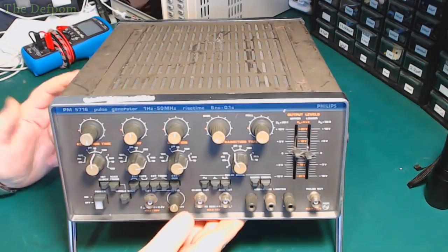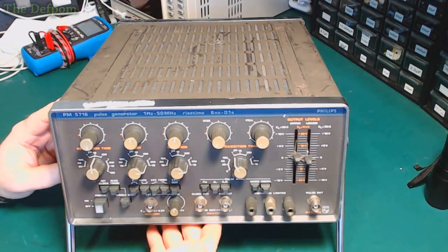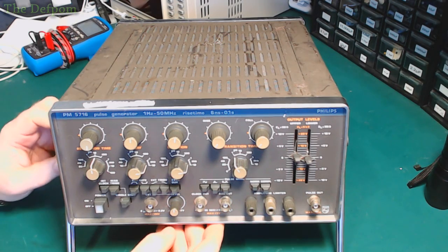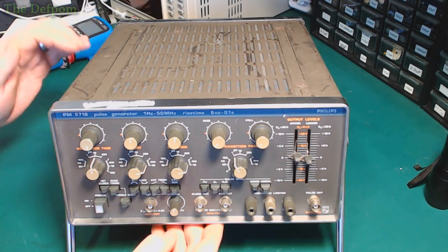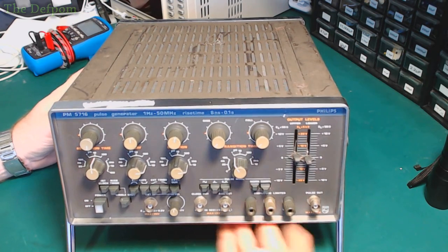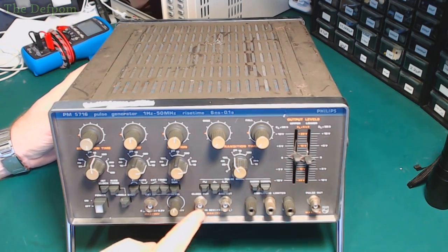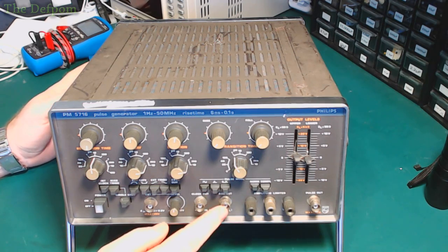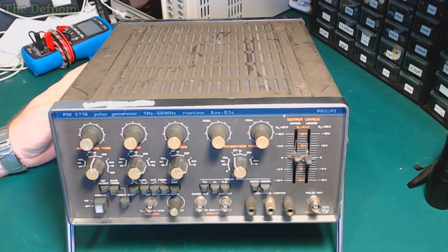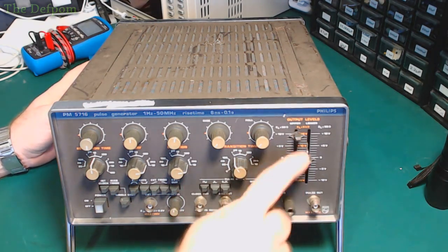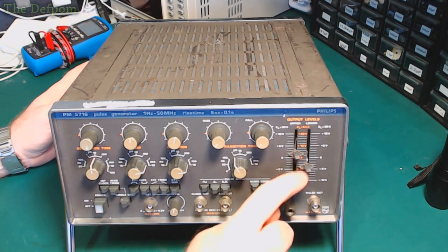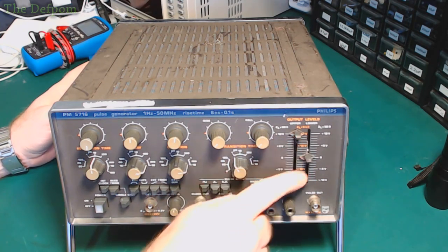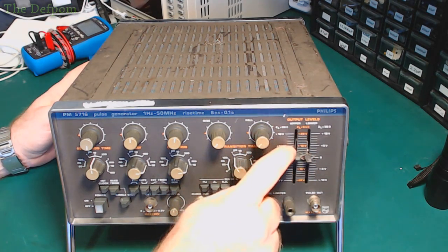There's a 5715 which is similar, but has some slightly different outputs on the front and stuff like that, so it's got a slightly different architecture, I think. But it might be similar enough to actually use as a diagnostic process for this thing. So the pulse output here doesn't work. The sync output does work. Aux, I don't remember. I think it kind of worked in some circumstances. And these are like split rail, so you can adjust the pulse voltages using this. And you can see they're tied together. So you can only do like a maximum of like 10 volts into 50 ohms.